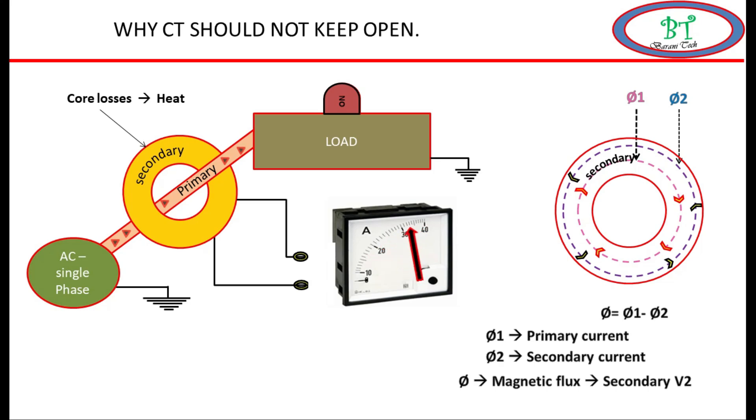In case the secondary current flow path is broken, due to this the current will not flow, so the opposite flux phi-2 is not produced. So the main flux equals the net flux, which causes high voltage at CT secondary.